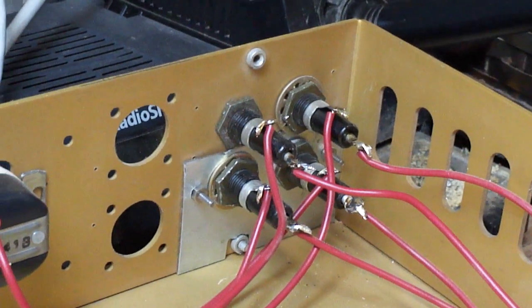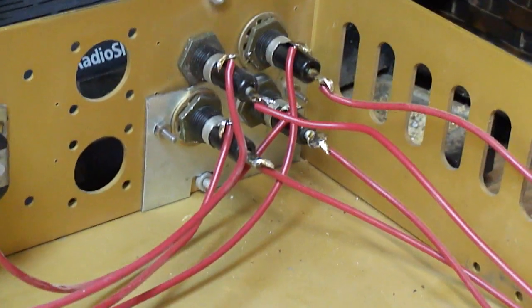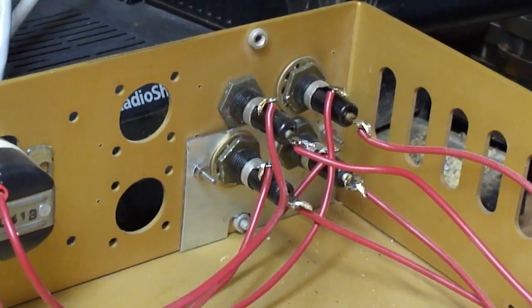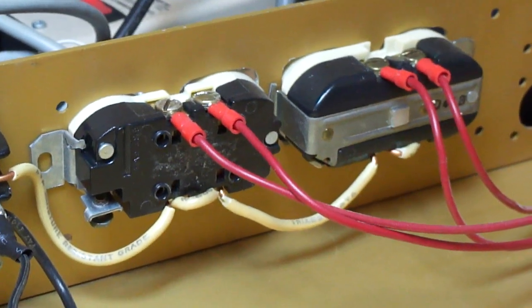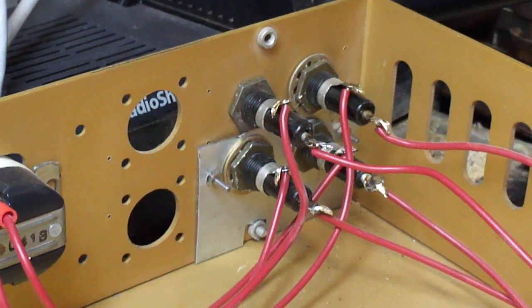Whoever built this had 15 amp fuses in these. Really they should probably only be about 5 or 7 or so, because you're not going to be drawing 60 amps out of this unit. You need to size the fuse so that it provides a reasonable amount of protection for each device.